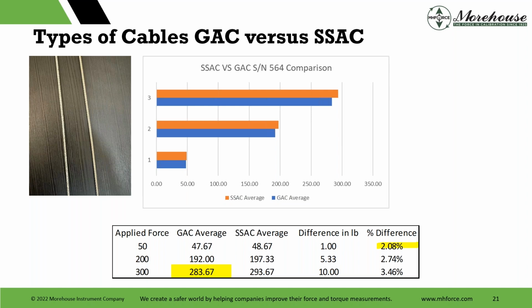And the highlighted figure shows the 1 point that doesn't meet, which would have resulted, so this is the problem, if you're using different cable, it would have resulted in a failed calibration and an adjustment when the tensiometer is actually within specification. So using the wrong cable has its own apparent risk. I'm thinking not many people are doing that because it is called out. Barfield calls it out in their manual, and some other manufacturers do.